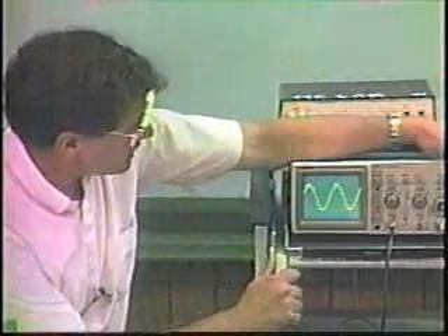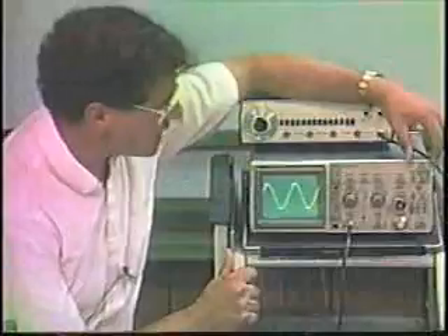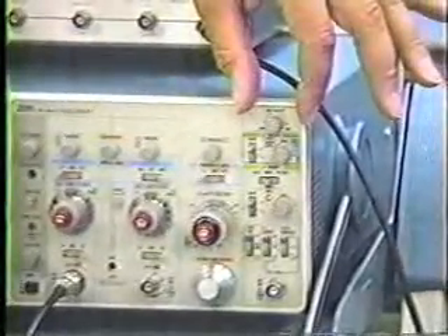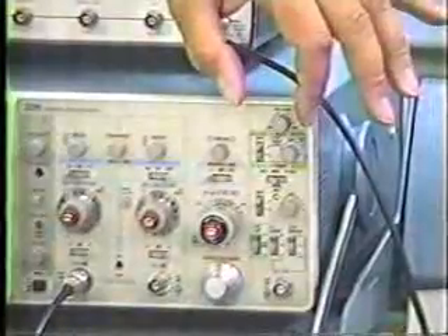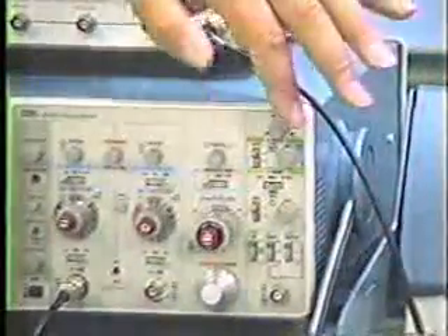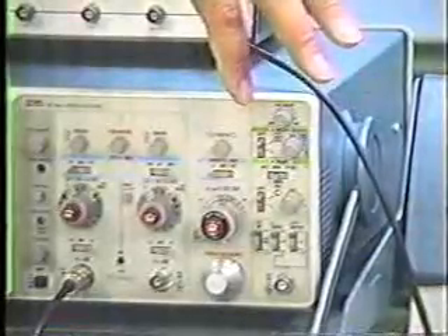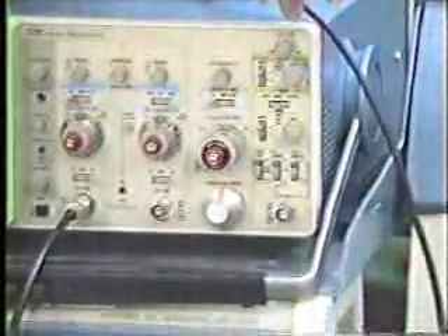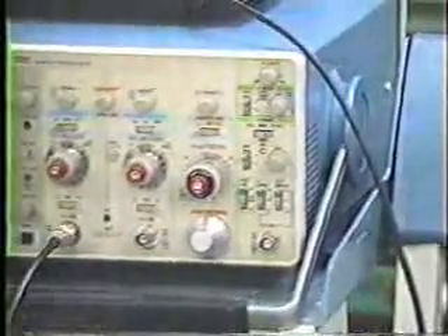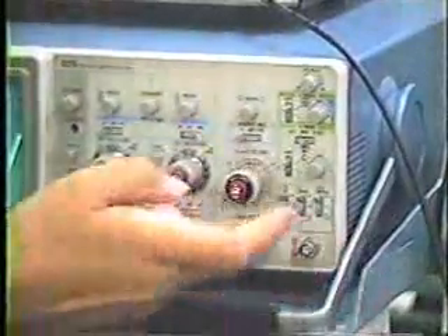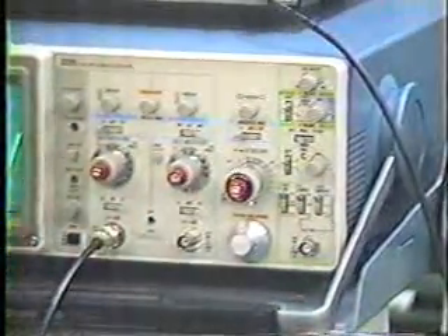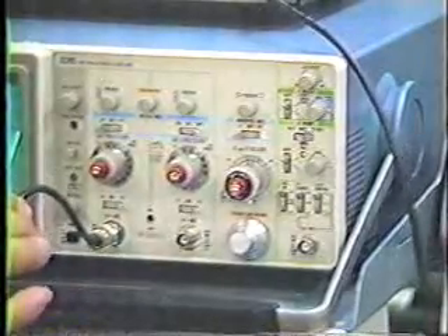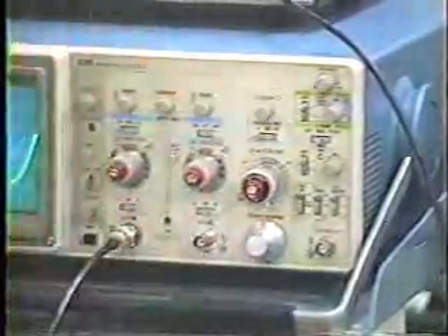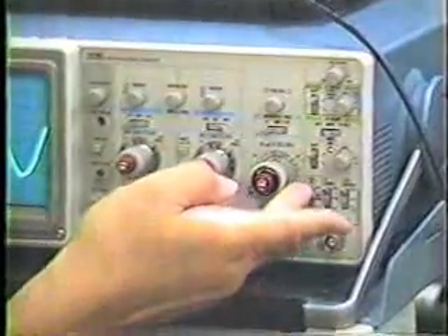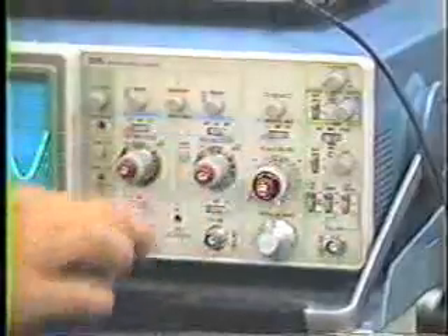So in order to trigger, we need to look at the right-hand side of the oscilloscope. Over here, the furthest right range on the face of the oscilloscope, you'll notice that there are a number of different controls. Don't be intimidated by all of those controls. Some of those are not going to be used very often. Most importantly, you want to make sure at the bottom here that the oscilloscope is actually triggering on the input that you've connected. You don't want it triggering on something else, or on the 60 hertz line. So this should be set to channel 1, because we're connected to channel 1.